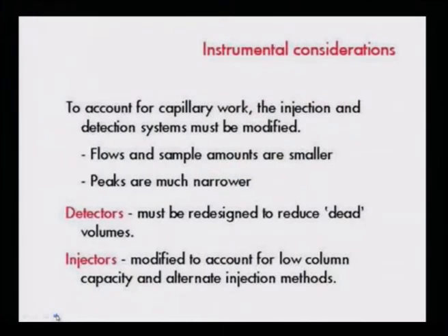So, there have to be certain modifications allowed for the capillary column to be fitted inside the machine, and therefore, the flow and sample amounts are much smaller in the case of capillary conditions. Peaks are much narrower, sharper. Detectors must be redesigned to reduce dead volumes and injectors modified to account for low column capacity and alternate injection methods.